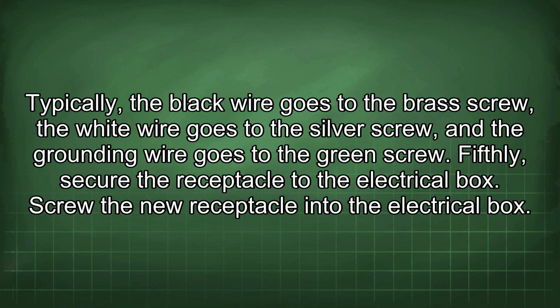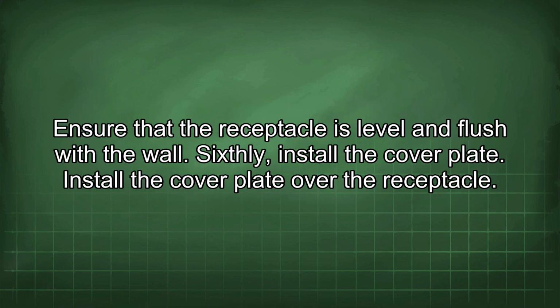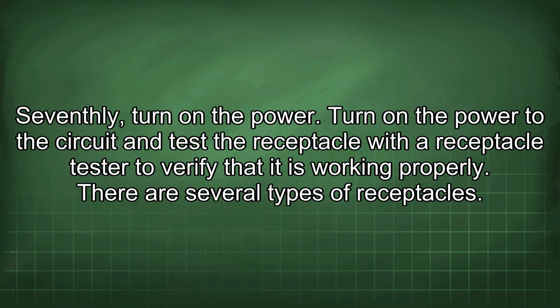Fifthly, secure the receptacle to the electrical box. Screw the new receptacle into the electrical box. Ensure that the receptacle is level and flush with the wall. Sixthly, install the cover plate over the receptacle. Seventhly, turn on the power. Turn on the power to the circuit and test the receptacle with a receptacle tester to verify that it is working properly. There are several types of receptacles.